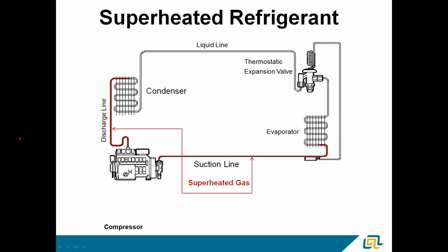Superheated refrigerant exists in two spaces on the system, but we're really only worried about one of them. The outlet of the evaporator to the inlet of the compressor through the suction line is superheated vapor. Superheat at the compressor should never exceed 20 degrees. Should have about a return gas temperature of less than 65 degrees. So if you got 70-degree superheated gas entering that compressor, it's not going to have enough cooling ability, and you're going to overheat that compressor. And it's really the hardest thing that compressor can do.